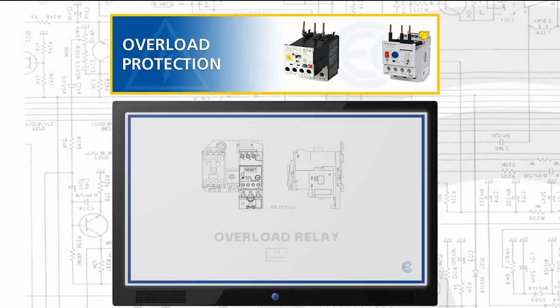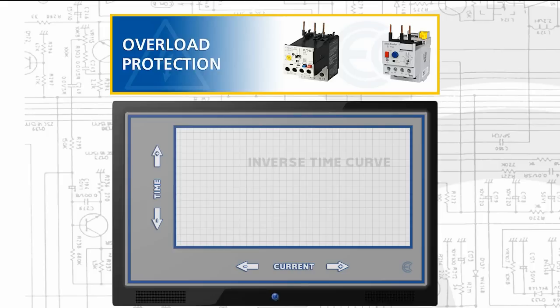Overload protection is protection against a running overcurrent that would cause overheating. Overload protection typically operates on an inverse time curve where the tripping time becomes less as the current increases. This means an overload relay isn't going to trip on momentary or short term overcurrent events that are normal for the piece of equipment it is protecting.